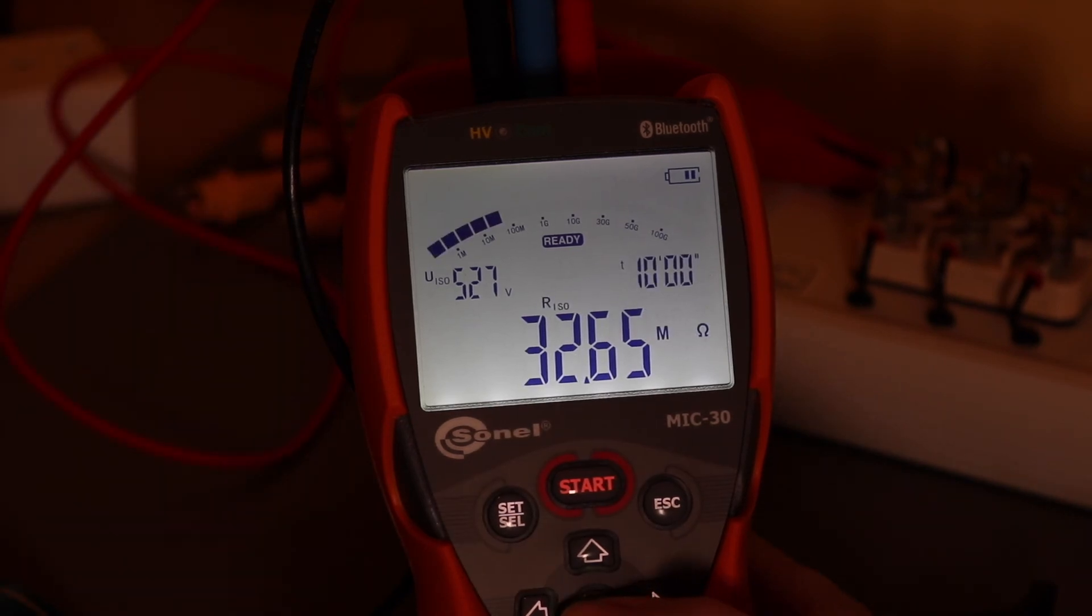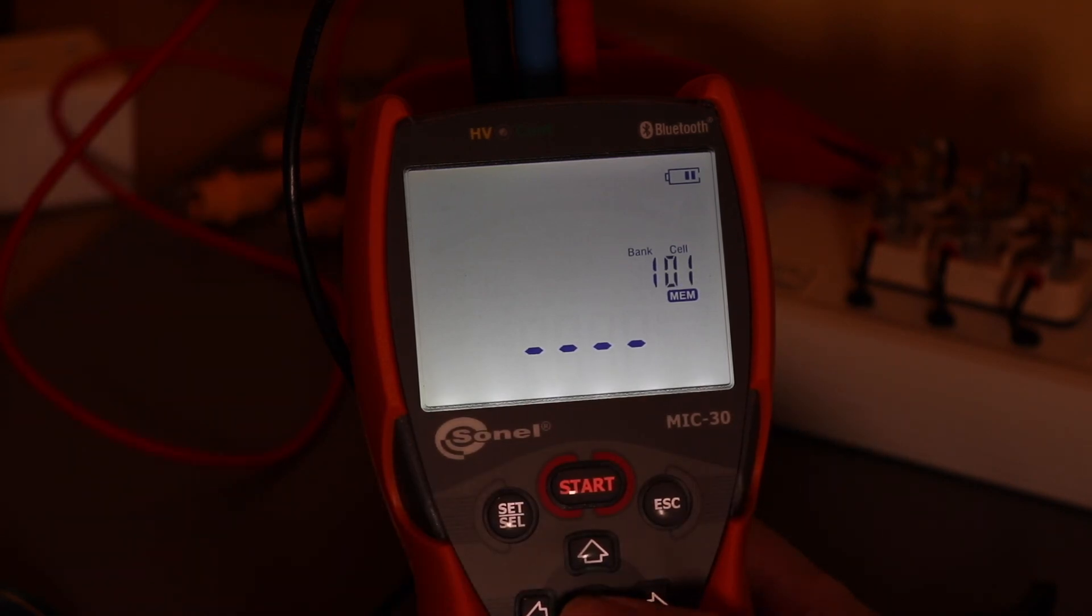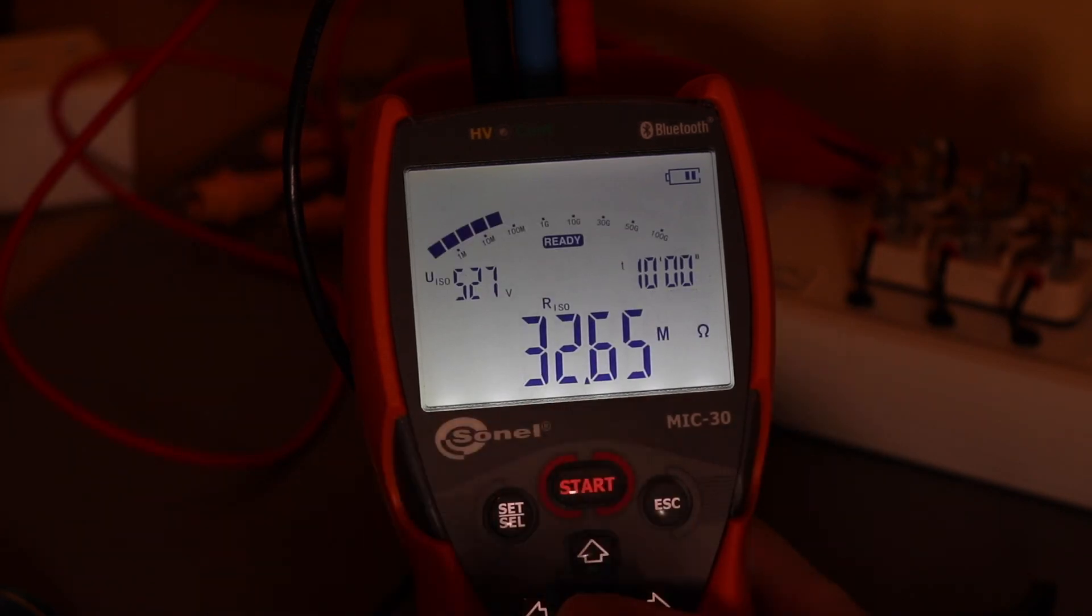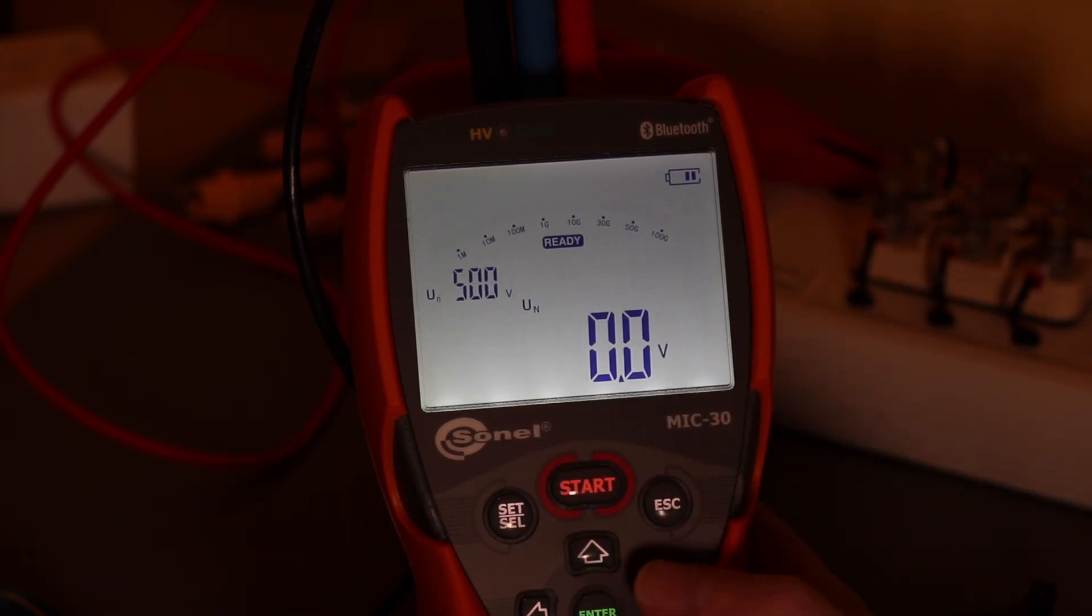And then to save all of those we'll hit the enter key. We can go back to the bank. If we want to change that or we've run out of number of cells but I've got nothing used in this memory. So just hit enter again. And it goes straight into that memory cell. And that is a polarisation index test completed using the Sonel MIC-30.